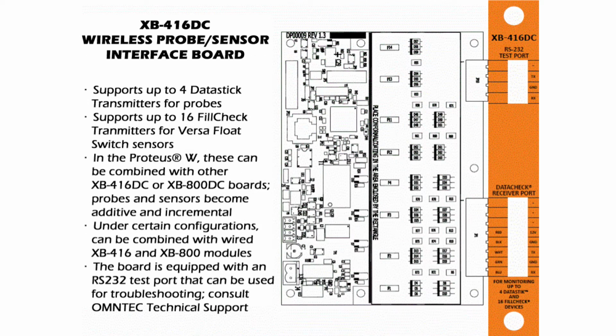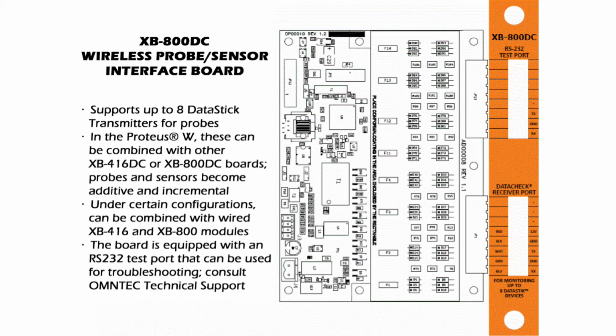The XB416DC is the wireless version of the XB416 and performs the same functions. However, information is sent from the tank, or the transmitter, to the controller, the receiver, via radio transmissions. This unit gets installed in the Proteus X and is referred to as the Proteus XW. The XB800DC is the wireless version of the XB800 and communicates via radio transmission. Both the XB416DC and XB800DC are equipped with RS-232 communication test ports to assist with troubleshooting radio transmission issues. In special cases, wired and wireless interface boards can be installed in a single Proteus X unit.